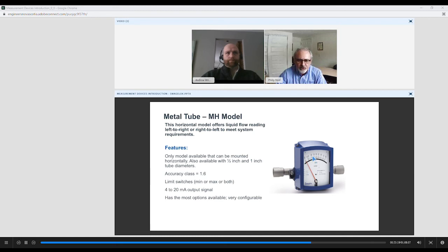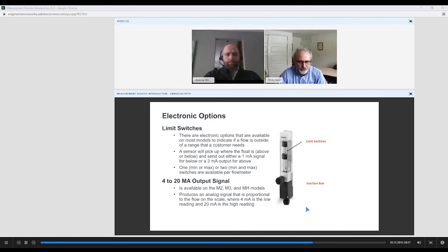These can be set up with limit switches inside, so you can have a high and low, and let's use that 4-20 milliamp output signal again and have 4 set as our low and 20 as our high. This has a tremendous amount of what we call configurable options. So it's very configurable to the type of system that you're adapting to. Limit switches, as I talked about, are available on the glass tubes, are available in others, and that may be where you want an electrical signal again, letting you know that there's a high or a low in the system, or when you've reached a specific flow rate to stop something or go back to a control valve.